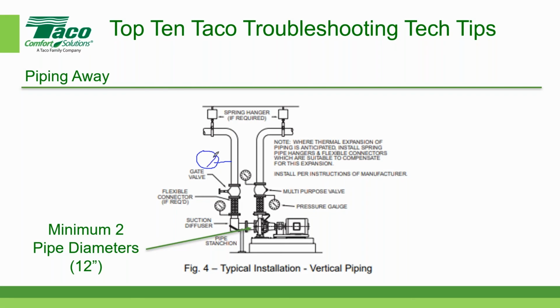And that pressure gauge does not tell us what the pressure drop could potentially be through this piping, through this valve, through this flex connection, through the end suction diffuser. It'd be much more accurate to make the connection right here at the flange port. Hopefully, I've seen many MEP detail drawings showing it on the pump. So if possible, I would recommend it, I think that's a good recommendation. Yeah, because if you don't, then you have to take into account the pressure drop, and that's not always that easy to calculate. It's much easier to measure than it is to calculate.